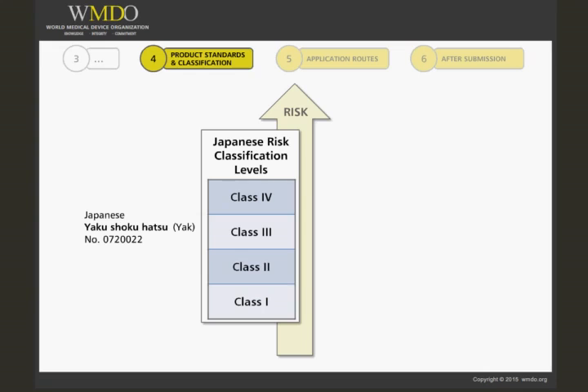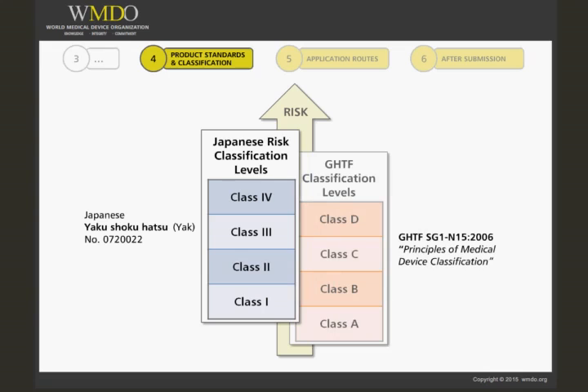YAK number 0720022 is almost identical to the GHTF SG1N15-2006, which gives you a matrix of criteria in which you can classify your device. The end result of the matrix is the risk classification of your device. The GHTF guidance has a device classification system of class A to class D, with A having the least risk. Similarly, the Japanese guidance has a classification system of class 1 to class 4, with class 1 having the least risk.